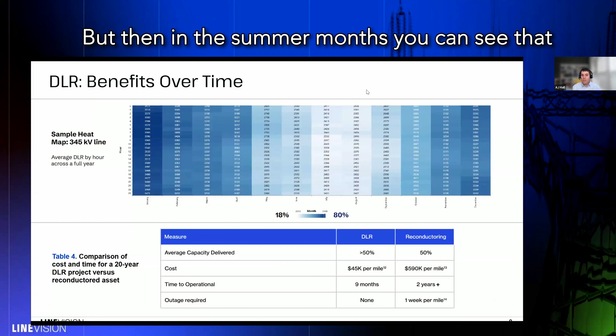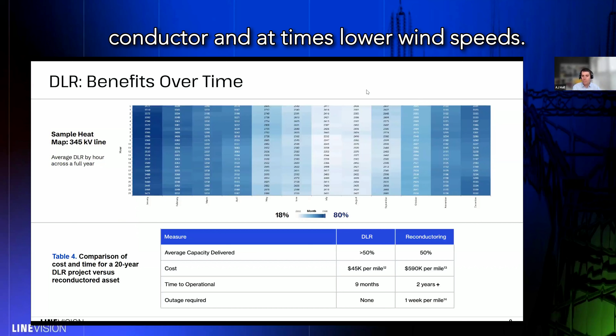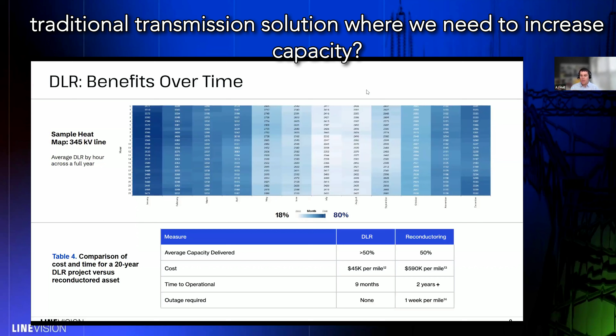But then in the summer months, you can see that DLR, while still achieving 18 to 20% above static, has less capacity due to the increased heat of the conductor and at times lower wind speeds. And so how do we compare this to a traditional transmission solution where we need to increase capacity?